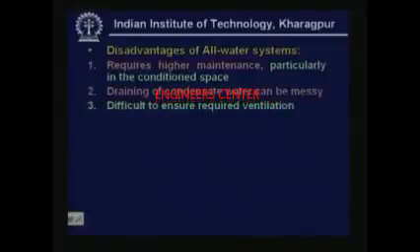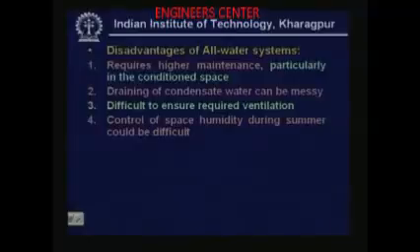It is also difficult to ensure required ventilation under all conditions. In all water systems, particularly when using a fan coil unit, you rely on natural methods for ventilation such as open windows or wall openings. The amount of outdoor air provided will not remain constant, as it depends on wind and stack effect. Additionally, control of space humidity during summer could be difficult, as you cannot get very precise control over space humidity, unlike in all air systems.